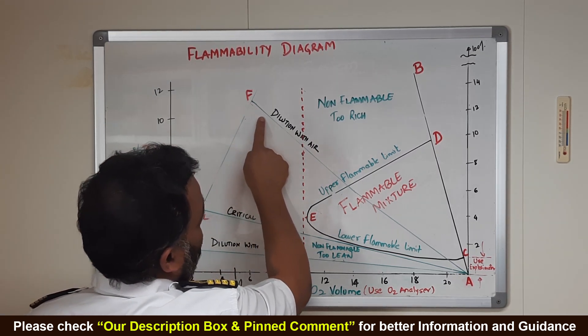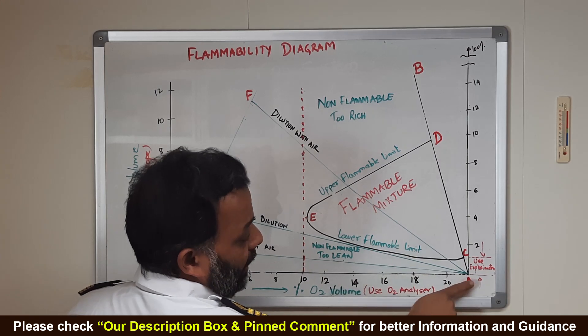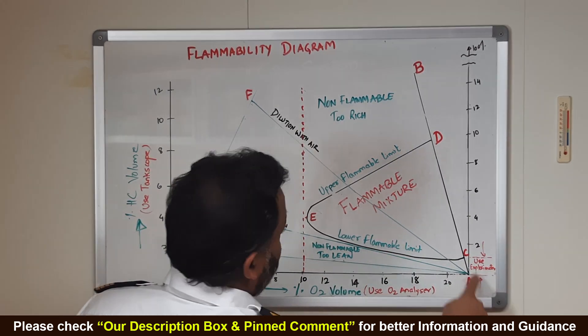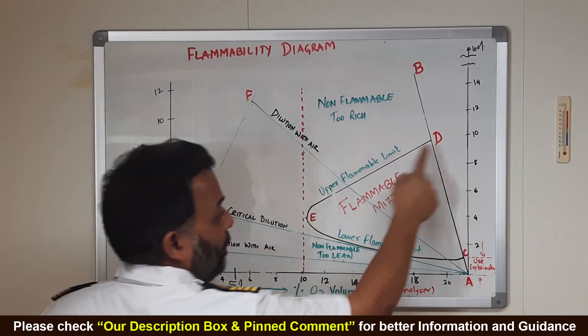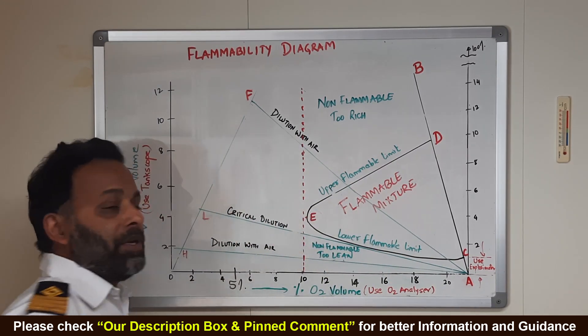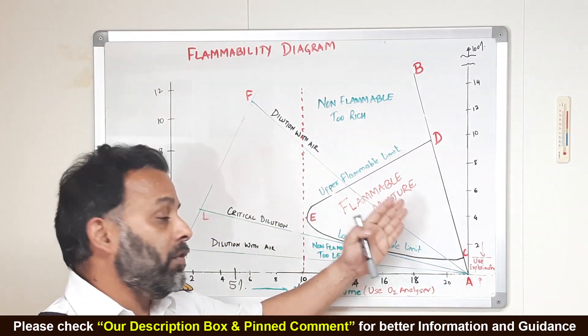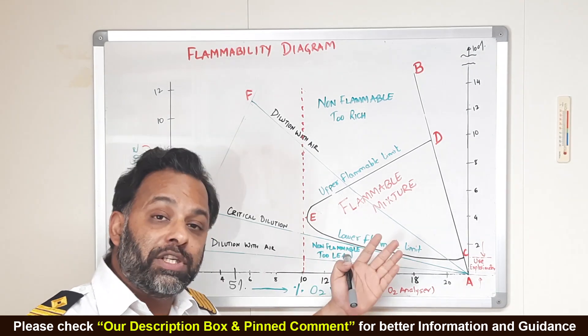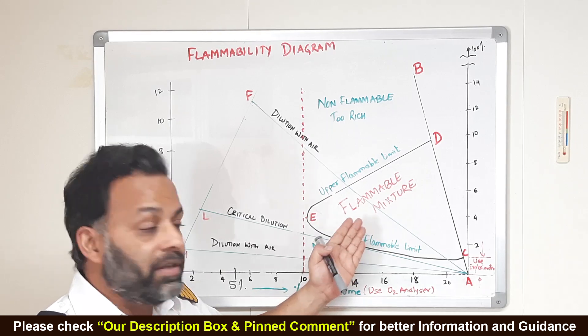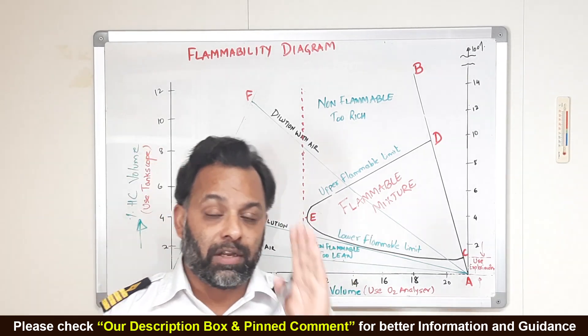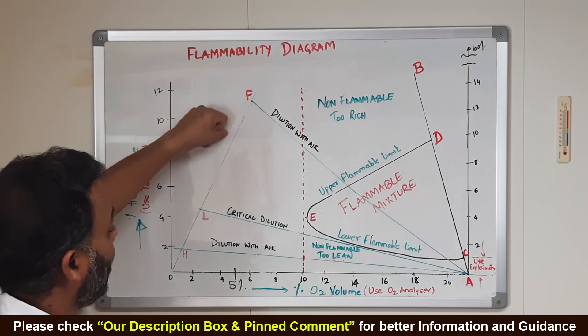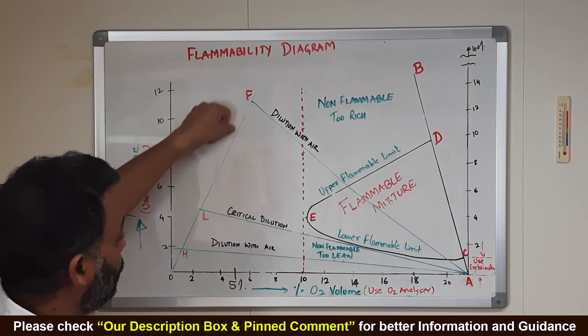And if it is at some point, let's say F, and we introduce air into the system, the atmosphere of that tank will go like this, where, ultimately, it will reach to 20.9% oxygen. But it will pass through this flammable mixture region. It is passing through this flammable mixture region, where the ratio of the hydrocarbons and oxygen is sufficient enough so that a fire can take place. This is hazardous area. This is what we do not want. So that is why, when we are discharging, we continue to pump more inert gas into the system. And we bring this point F to H.